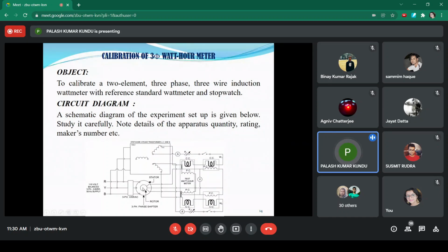The advantage is that the primary of this three-phase phase shifter and the step-down three-phase transformer are drawn from the same side. It is a parallel connection. But the secondary of the step-down transformer as well as the three-phase phase shifter are different. What is the meaning? That means the secondary of this stator winding is phase shifted with respect to the primary voltage. In fact, there is a three-phase phase shifter, an induction regulator type three-phase phase shifter. What is the induction regulator type phase shifter?